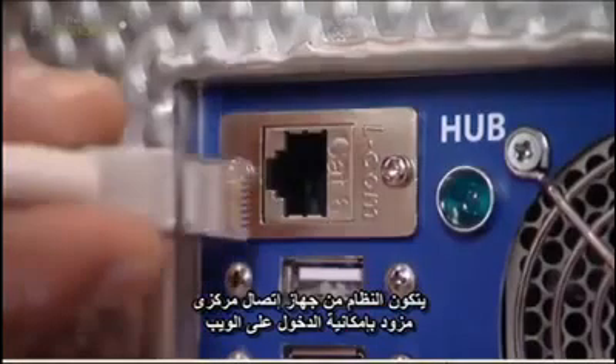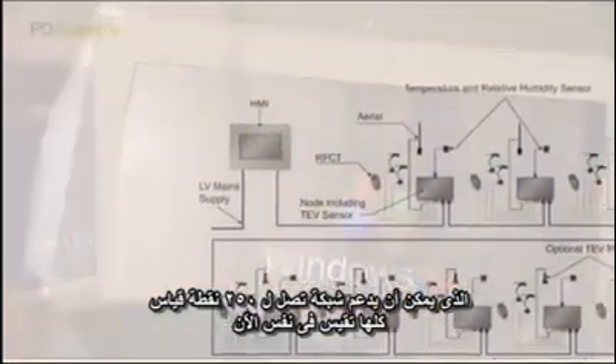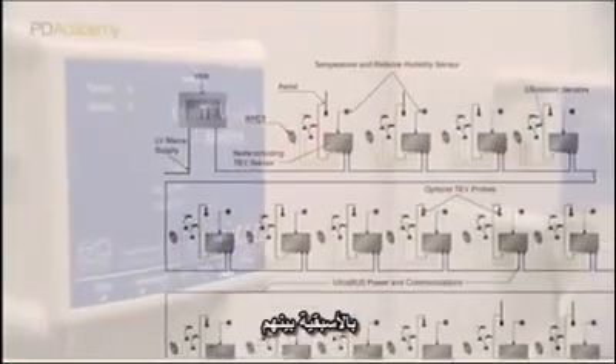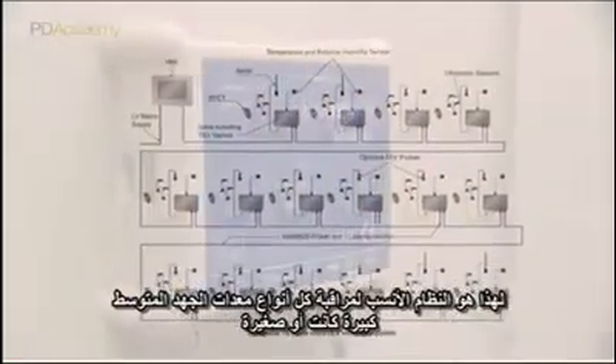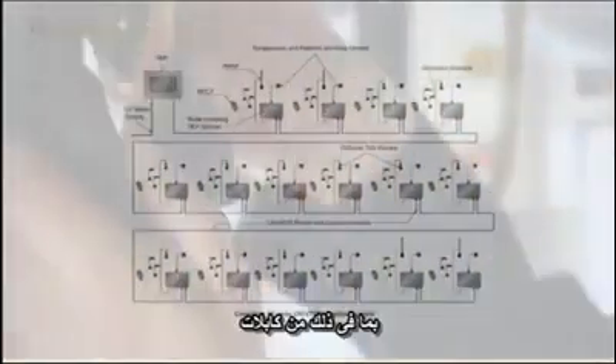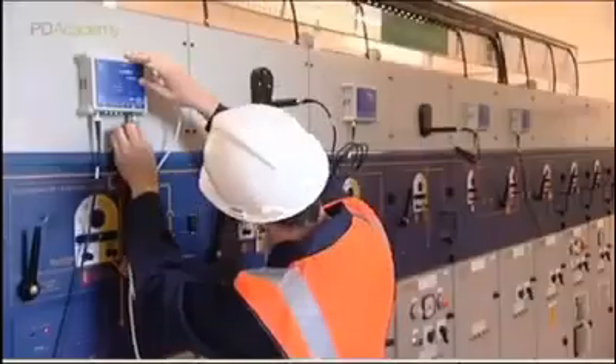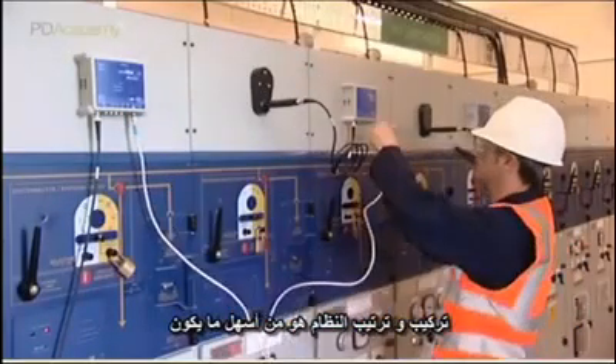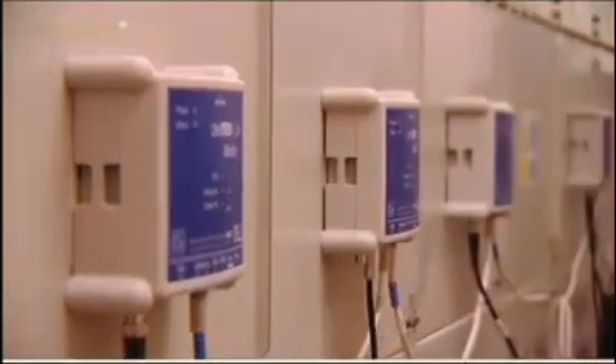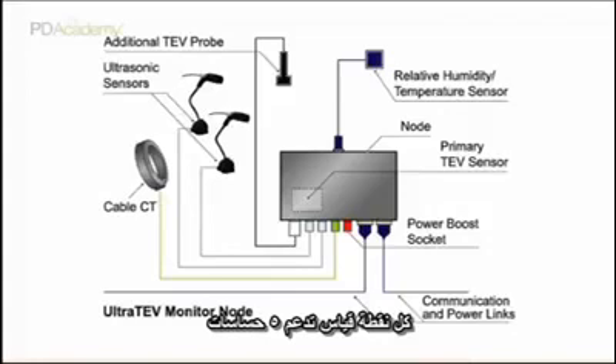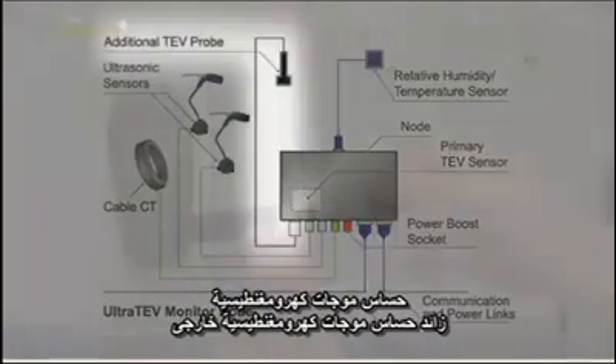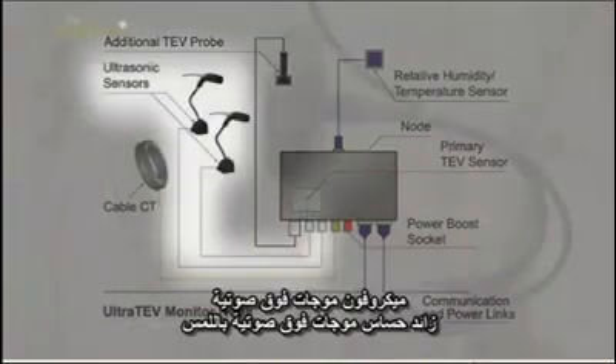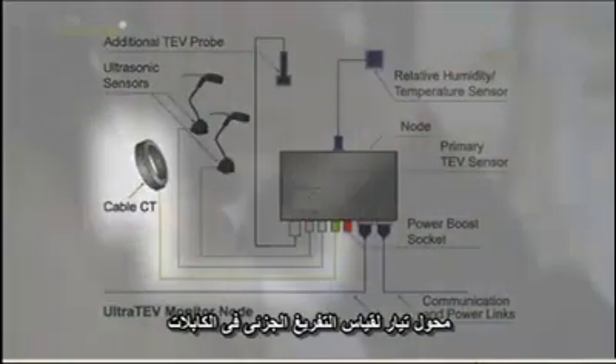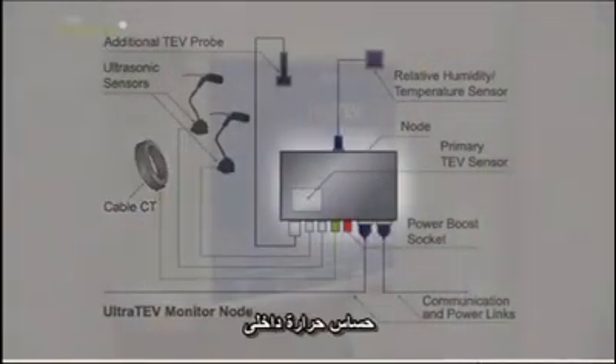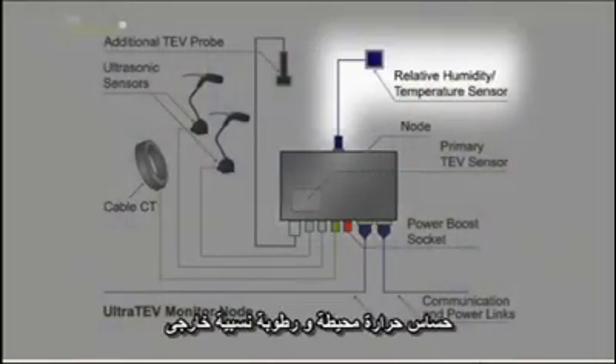The system comprises a web-enabled hub that supports a network of up to 250 measuring points simultaneously, all with precedence between them. So it's perfect for monitoring all types of substation assets, large or small, including cables. Installation and configuration are both very simple, because it uses a new networking solution which carries both data and power over a single cable. Each measurement node supports five types of sensor: a built-in TEV sensor plus additional plug-in TEV probe, an ultrasonic microphone plus additional contact probe, a plug-in radio frequency sensor for measuring PD in cables, a built-in temperature contact sensor, a plug-in ambient temperature and relative humidity sensor.